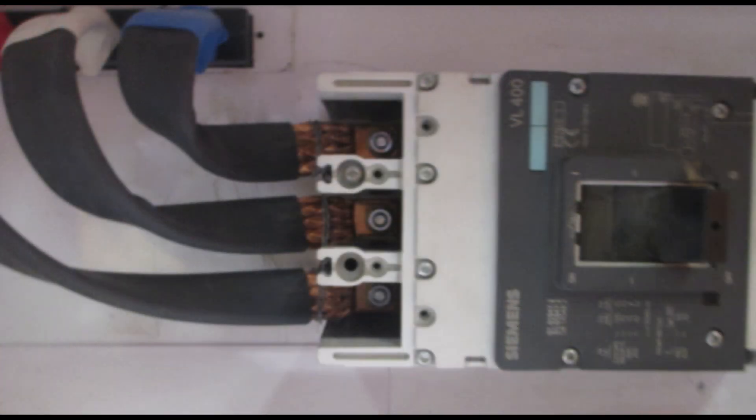Note that fuse wire has been connected across the phases on the line side of the protective device. As soon as the test supply is applied, the fuse wire vaporises and an arc is established. The resulting ionised gases create a substantial increase in pressure inside the switchboard compartment. This tests the ability of the compartment and the switchboard to contain the fault.